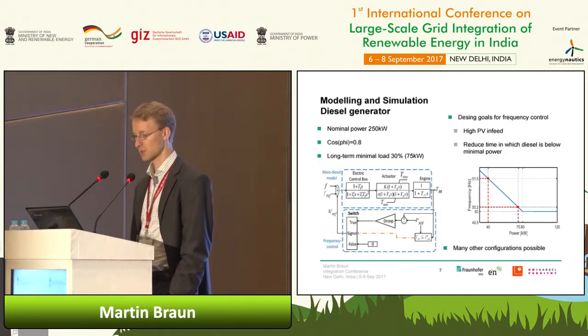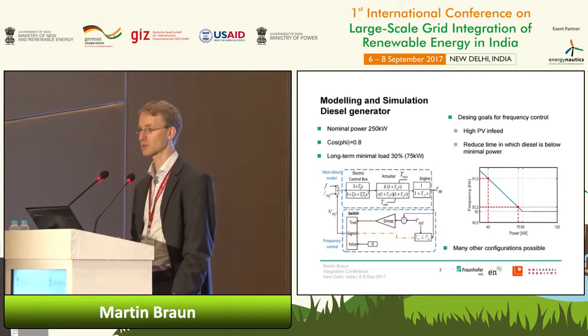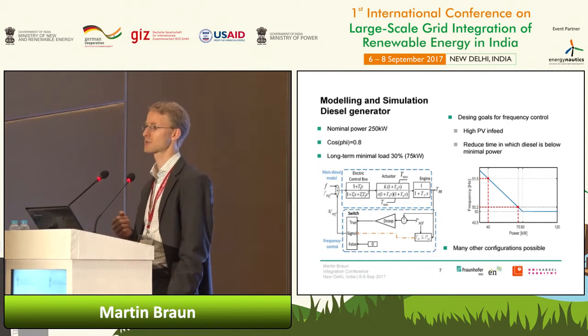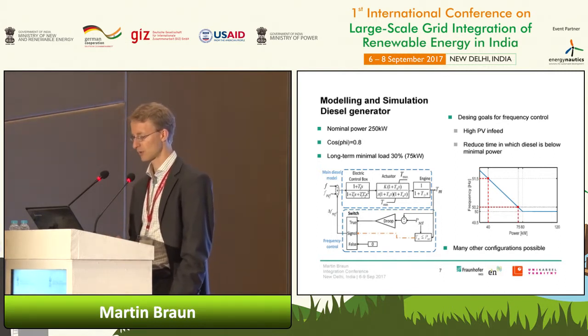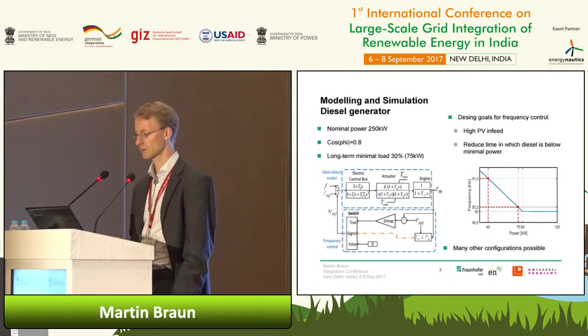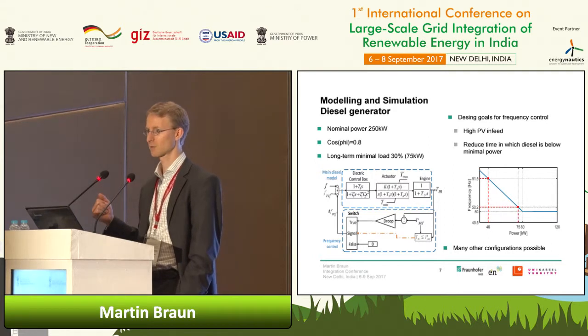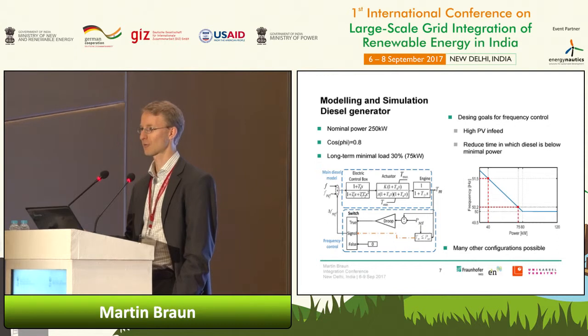We also simulated a diesel genset according to literature values and a certain validation of the control signals. And so the idea here is that we have the frequency as a control signal. This is often done without communication, the frequency being used as information about the active power balance in the system. So if the 250 kilowatt unit is going below 80 kilowatt, which is kind of the minimal operational limit, then it's going to increase frequency in order to give the PV plants the information that they should better reduce their active power feed-in, in order to leave the grid forming unit, the diesel genset here, under operation and not go into an underloading situation. So you can parameterize this depending on your situation.